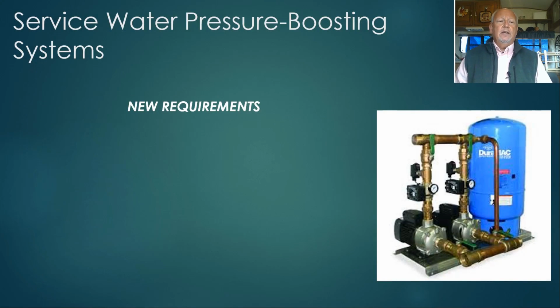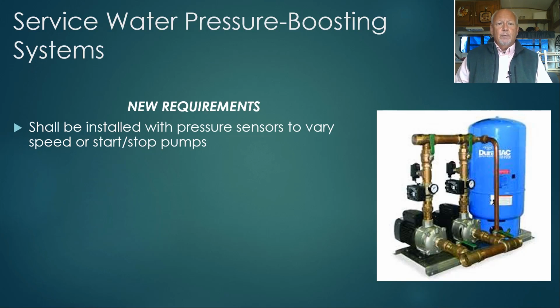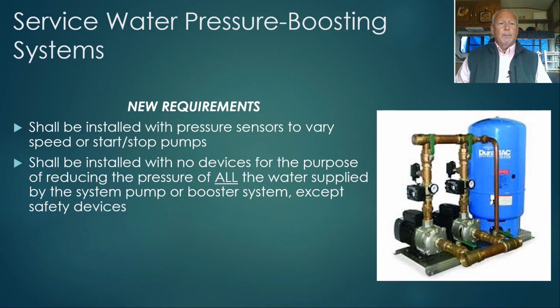Another change in the 2018 Washington State Energy Code refers to service water pressure boosting systems. So there are new requirements for pressure boosting systems on service water heating systems serving buildings. They shall be installed with pressure sensors to vary speed or start up pumps. They shall be installed with no devices for the purpose of reducing the pressure of all the water supplied to the system, except safety devices. This is important. You can still have balancing valves or circuit setters on branch piping serving different risers or areas of the building, but you shall not have a pressure reducing device downstream of the pump that regulates the water pressure for all of the water supplied by the system.